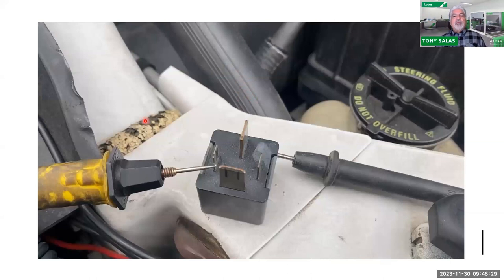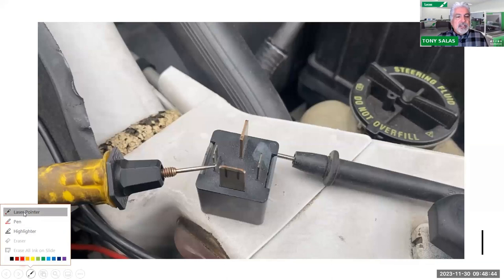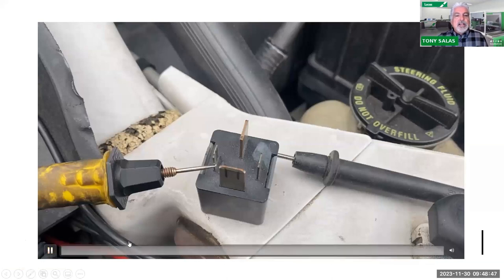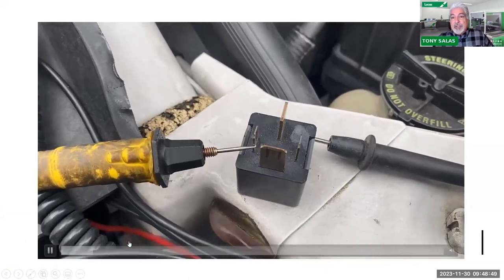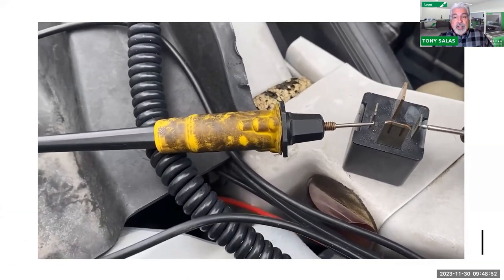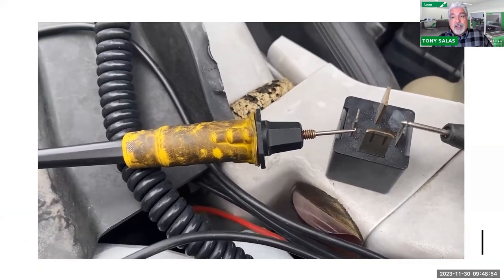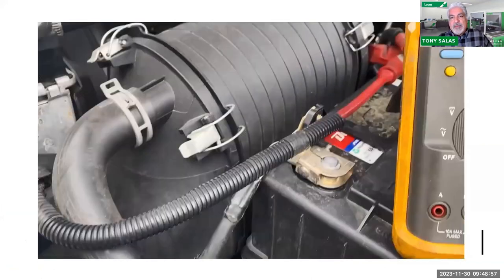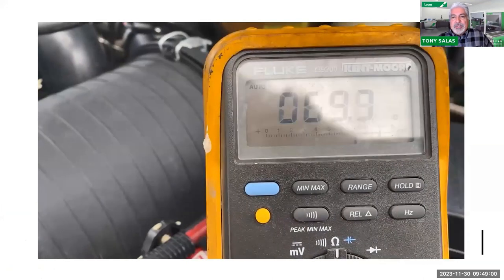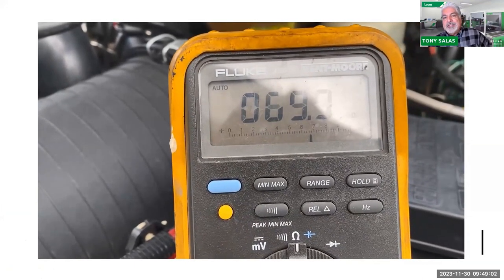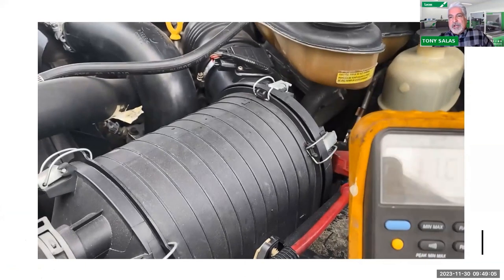But when you're looking at the relay itself, you can also test the coil side, because the coil can be shorting. In this case, we can take known relays and know what the resistance is. Here you can see I'm actually measuring the resistance. Let me get rid of this again. I'd like to probe because they could be shorted - if it is shorted, relay coils can be shorted, so therefore they're making contact there. I'm trying to do this one hand and hold the camera at the same time, but in this case you could see the resistance is roughly 70 ohms. I'm trying to keep my hand steady there, but we're measuring about 70 ohms right there.